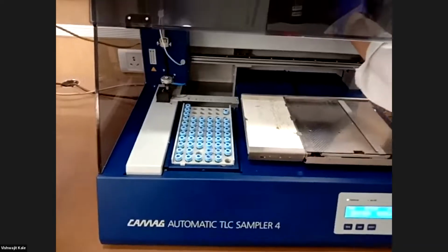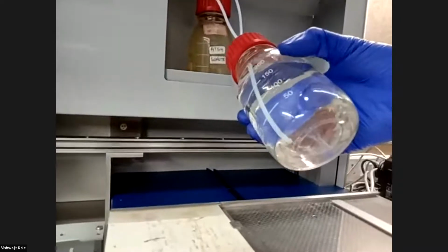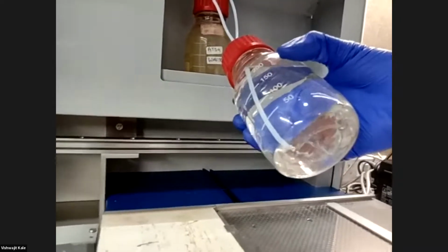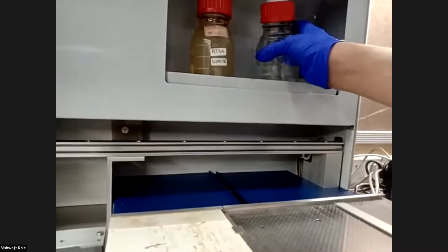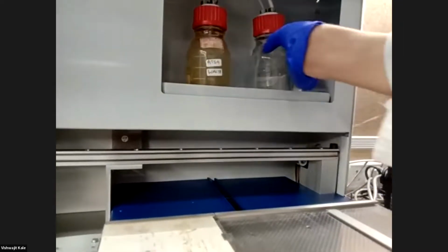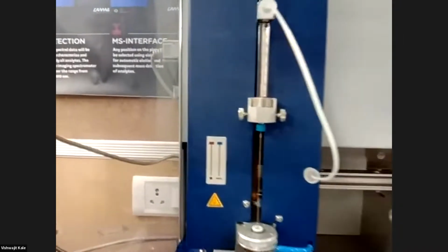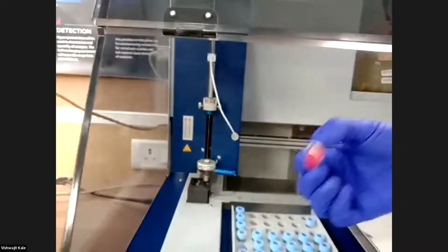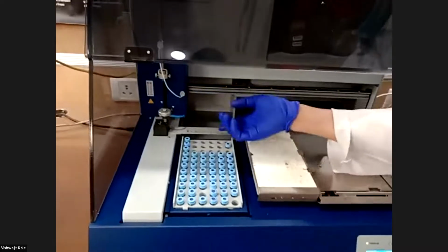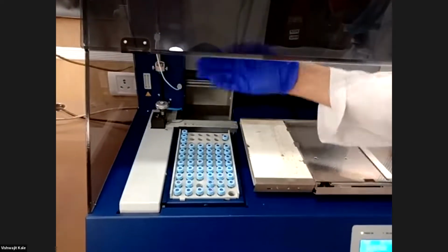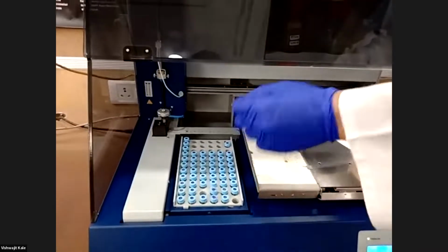And here two bottles are given. This one bottle is filled with methanol. Methanol is like a universal solvent in which many compounds are soluble. So we are using methanol in daily practice to clean and rinse the syringe. From this methanol, the syringe will automatically get rinsed, and after application of one sample from one vial, syringe cleaning is automatic. Then syringe filling with the second sample is also automatic.